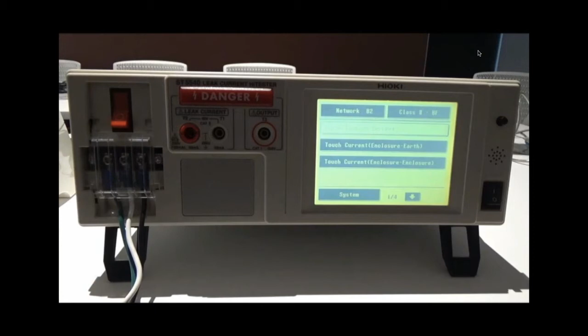If you want to check the details, press the All key. If you want to check the second result, press the Mode key and then the All key. We can see the results of the second patient leakage current of patient to earth.